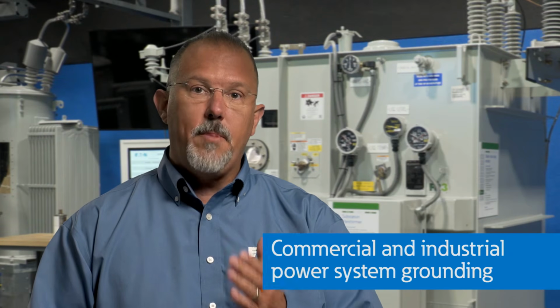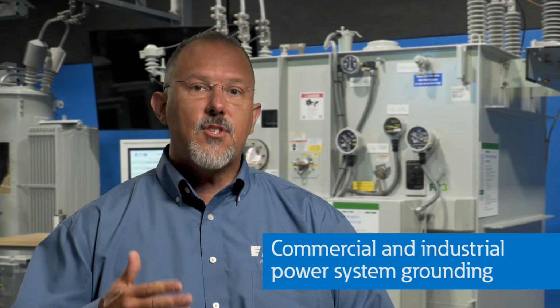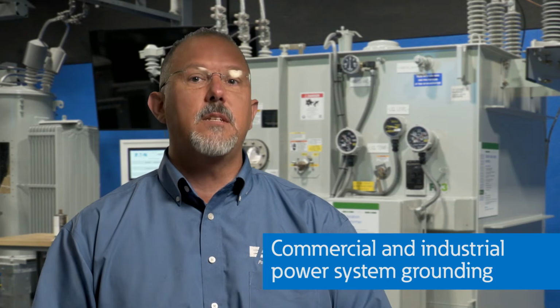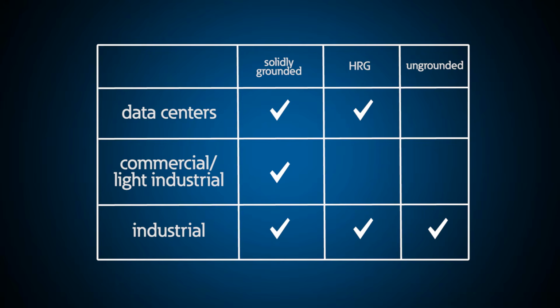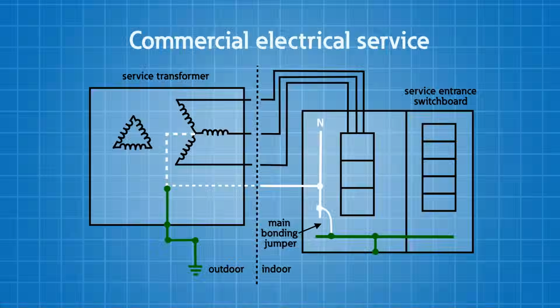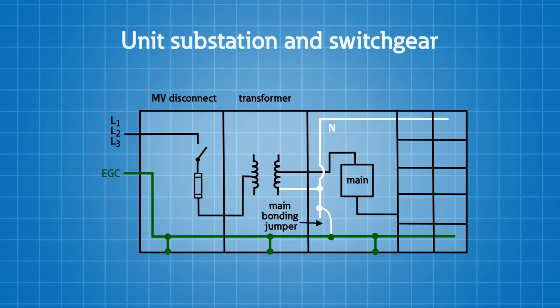So now let's look at a commercial power distribution system. As you get outside the residential world, you have more options based upon the applications. For example, data centers and other systems that demand higher service continuity may opt to use high resistance grounded systems as opposed to solidly grounded systems. Many commercial and light industrial systems will be solidly grounded. Let's show you how a pad mounted transformer might be grounded and bonded, and how the indoor switchboard might be grounded and bonded for a solidly grounded commercial power distribution system. Finally, for larger systems using unit substations and switchgear, here's how the grounding and bonding is done for those systems.